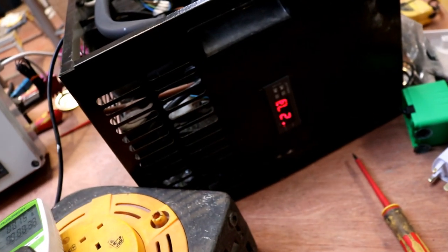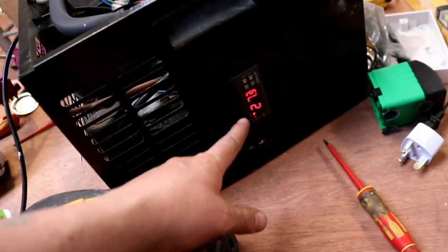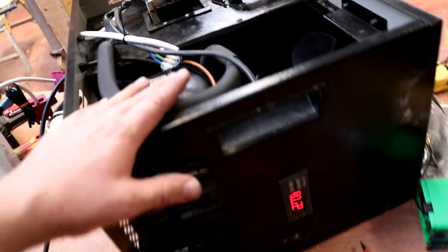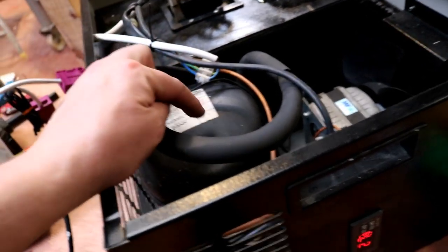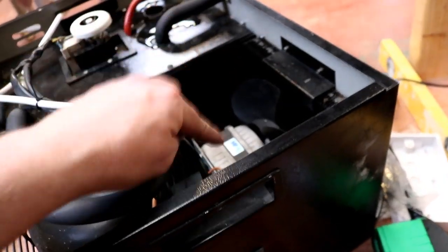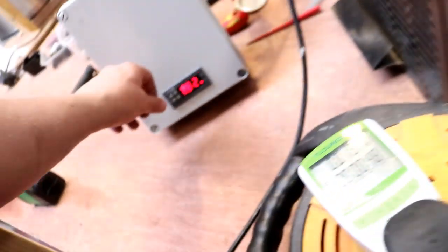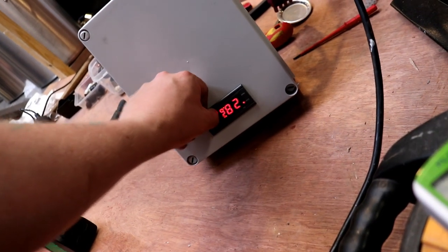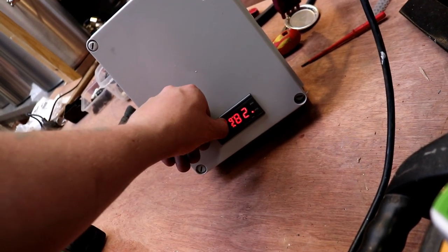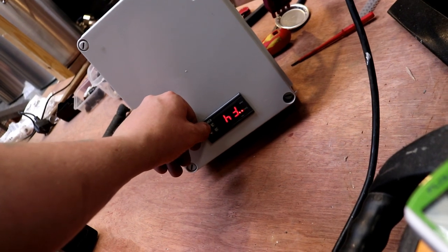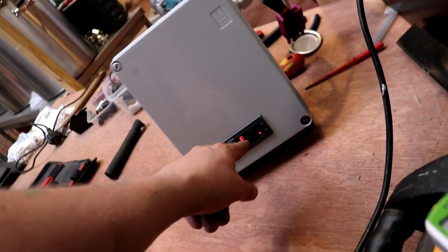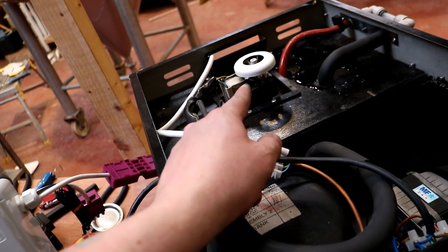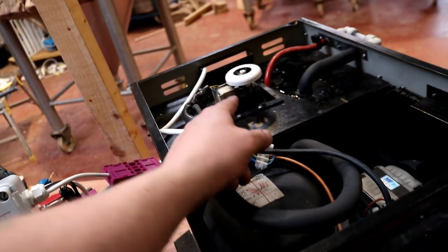Nothing else is happening. So now we've got a 5 minute wait for the compressor to kick in. And then when that turns on, the compressor will kick in and the fan will kick in. But having said that, this box may turn on before then, so we'll be able to see. Yeah, this will come on 2 minutes beforehand, so we'll be able to see what kind of current the recirculation pump's going to draw as well.